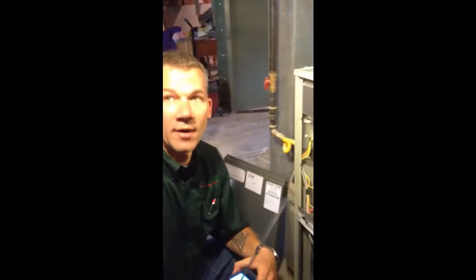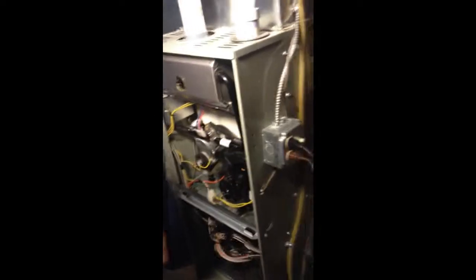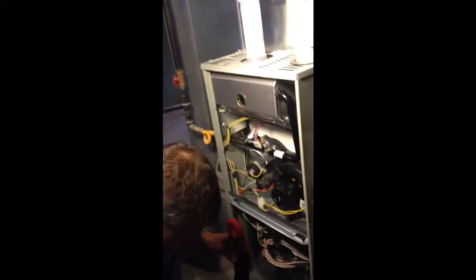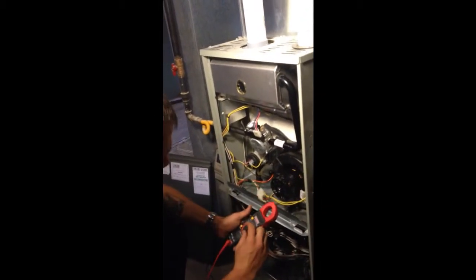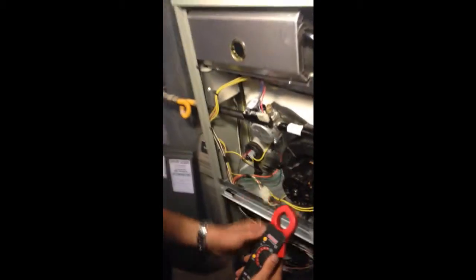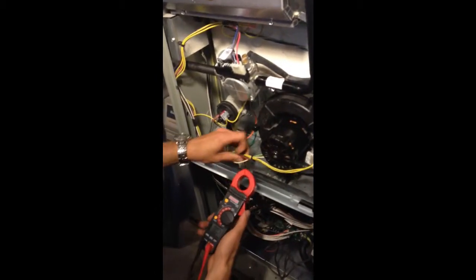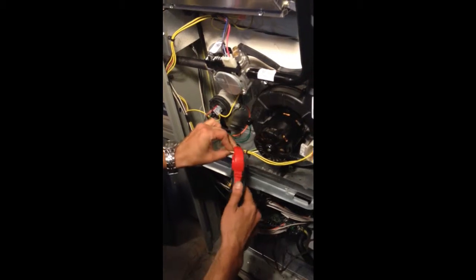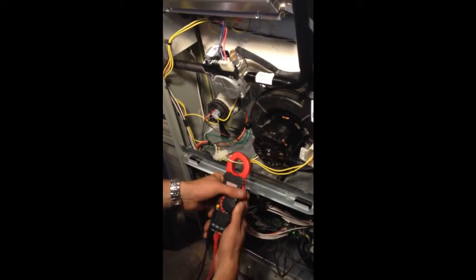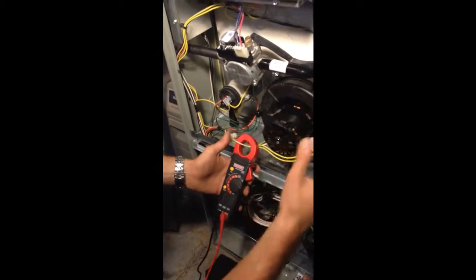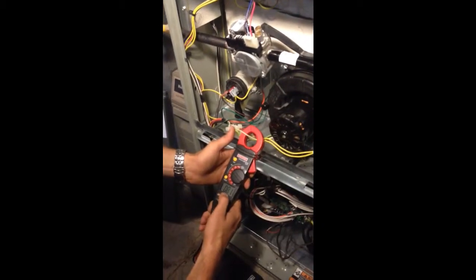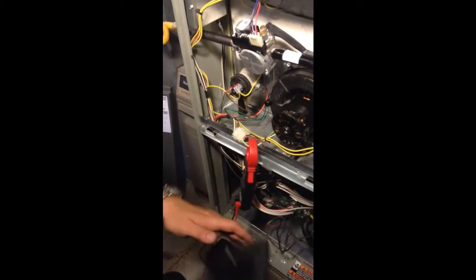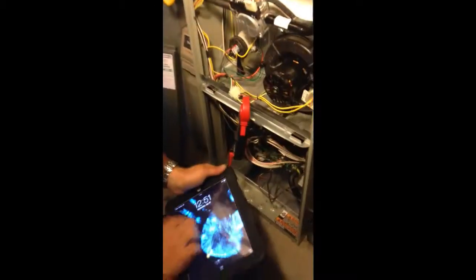When I'm outside and it's not running, I turn it on now because it takes like 60 seconds to warm up. And then we're going to turn the furnace on. I'm going to get my amperage readings from the inducer motor, exhaust motor, however you want to look at it. So it turns on first to establish an exhaust in the right pressure, and it's at 0.81 amps, which is normal. So we put that on our checklist.